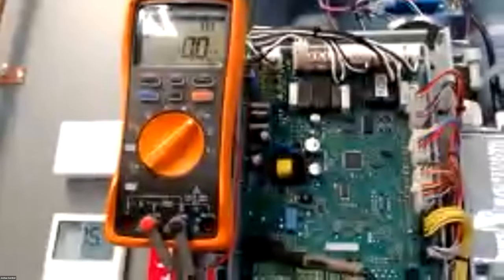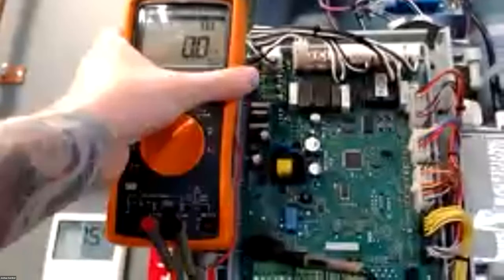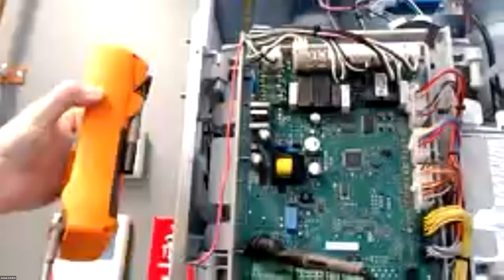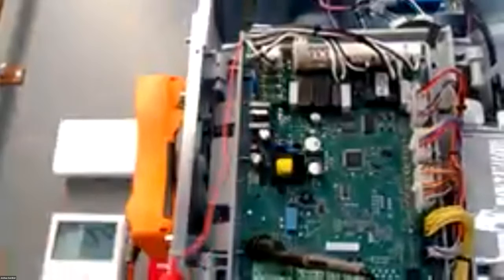So you can look at your ionization current through the control, but if you do it through a meter, it's more accurate. I know we say you can look at the ionization, but if you're really trying to troubleshoot, I will probably do a meter. That way I can look at the temp. And again, to do that is you have it set on your microamp and you run it in series.